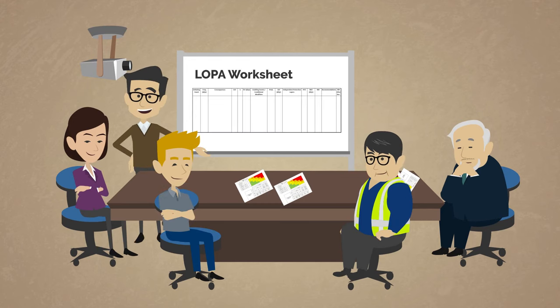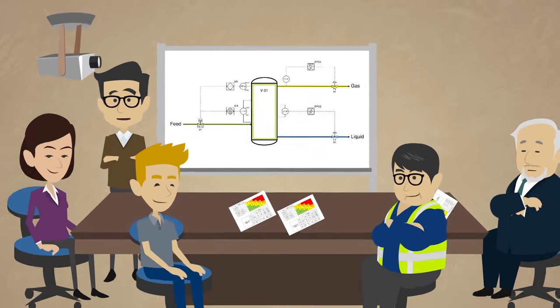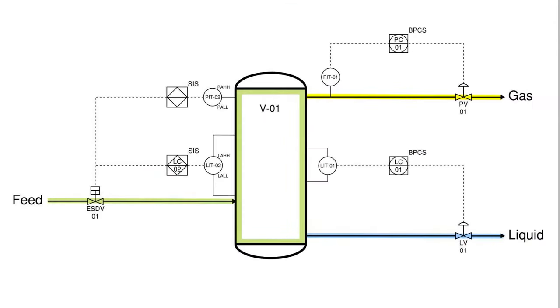Let's jump in with our HAZOP team as they conduct a LOPA to identify how they would determine the reliability of the SIF required for the vessel V-1 we have been looking at. Alright, we have identified that the level control valve LV-1 failing closed would cause liquid to carry over from the separator V-1 to the compressor downstream.